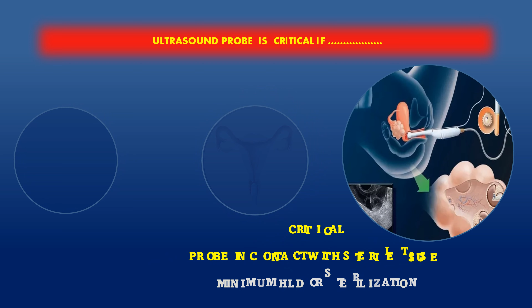It is important to remember that according to the Spaulding classification, an ultrasound probe can also be considered critical. It is a critical device if the probe comes in contact with sterile tissue, like using transvaginal ultrasound for egg retrieval in IVF pregnancy, or ultrasound-guided aspiration of an ovarian cyst, for example, or ultrasound-guided tissue biopsy. Here, the ultrasound comes in direct or indirect contact with sterile tissue inside the body. Minimum high-level disinfection or, best, sterilization is mandatory in this case.